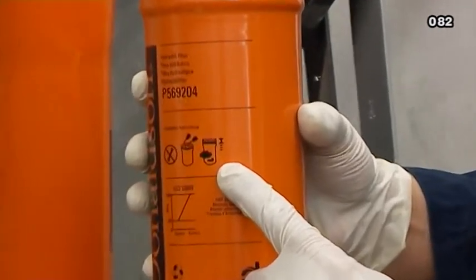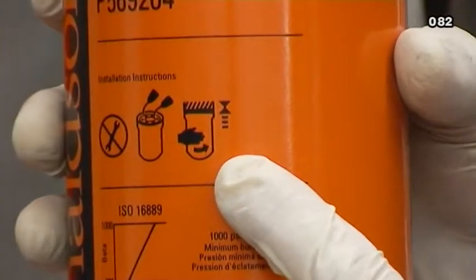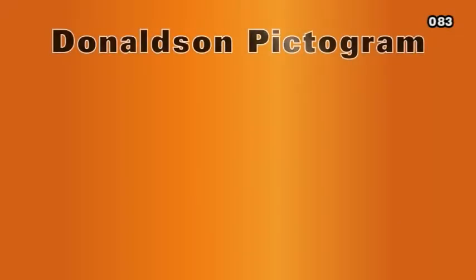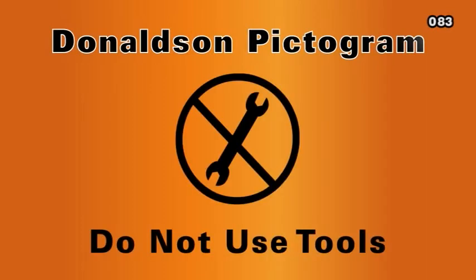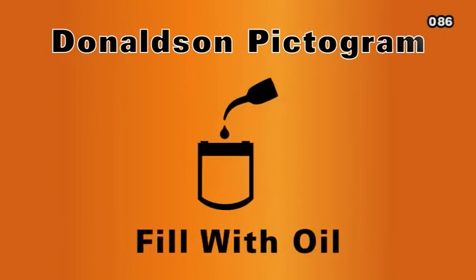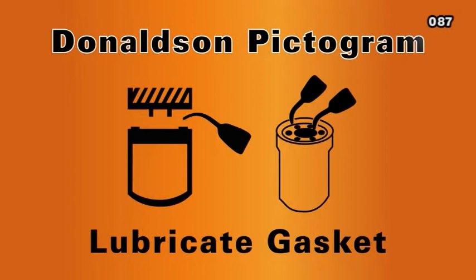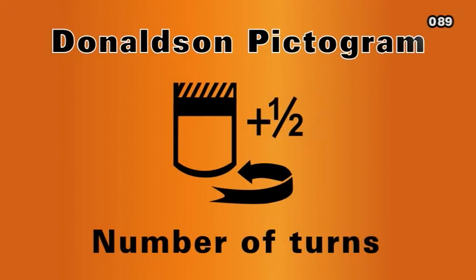Donaldson spin-on filters have pictograms on the side to define the service maintenance steps. To help you understand, here is a brief pictogram review. Do not use tools. Clean the filter base. Fill with oil. Lubricate the gasket. Hand tighten. Tighten the filter according to the instructions printed on filter.